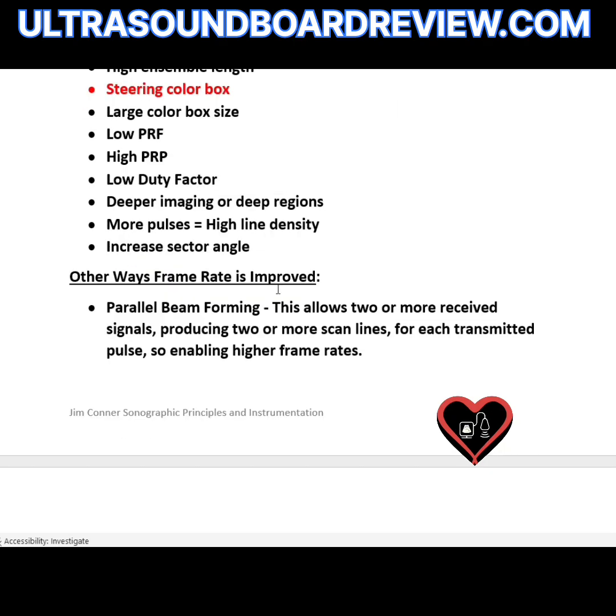One way that frame rate is improved is parallel beam forming. This allows two or more received signals, producing two or more scan lines for each transmitted pulse, enabling higher frame rates.